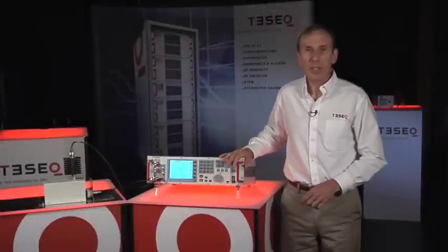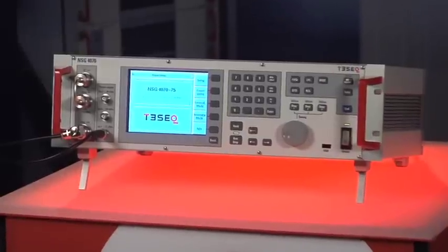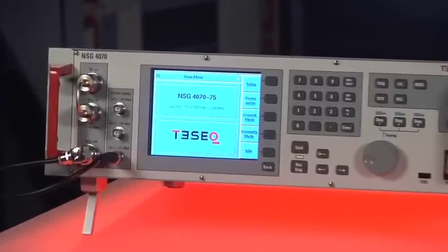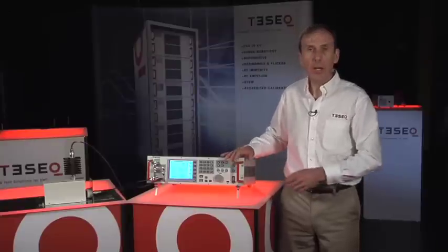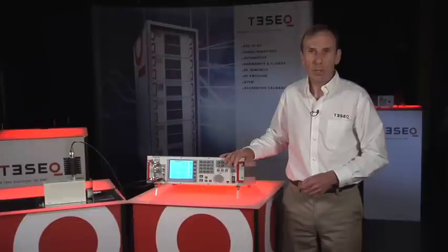Hi, welcome to TESEQ Live. I'm Greg Senko and I'd like to tell you about the NSG 4070. It's an integrated system for coupling RF interference signals onto product cables. It's a fully integrated, compact system for coupling using CDNs, EM clamp, bulk current injection, or direct injection test methods.